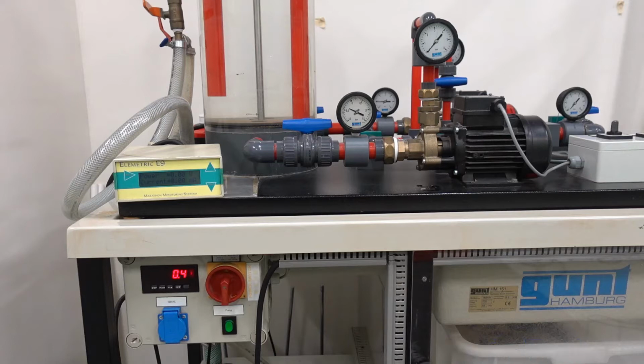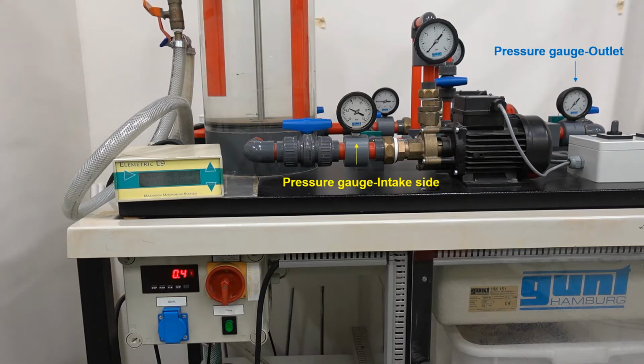The x-axis of the characteristic curve is volumetric flow rate. It should be measured by a flow meter, but in this experiment, the flow rate is measured by the mass of the water. We can use the mass of the water divided by its density to calculate the volume of the water. The pressure difference between the inlet and outlet side is measured by those two pressure gauges.